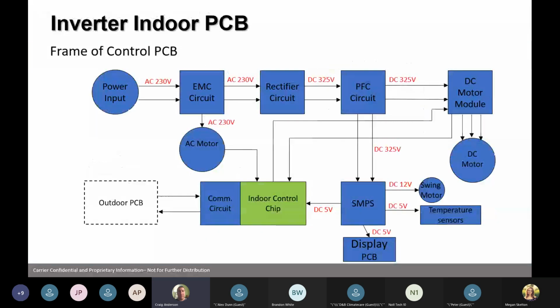So to give you an idea how this works, we're dealing with AC voltage and we're dealing with DC voltage. When the power comes into the unit, we want to be mindful of what's coming in, that it's not too high or too low. These units have a setting inside. Anything under 187, the unit will not start. Anything over 253, the unit will not operate. It's powered too much, so the unit will shut down.